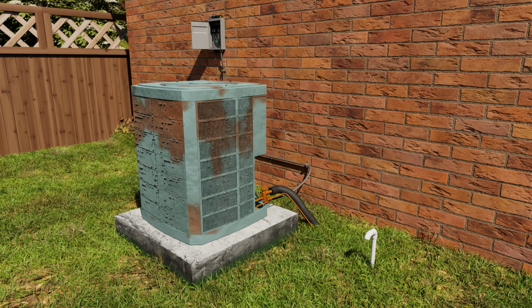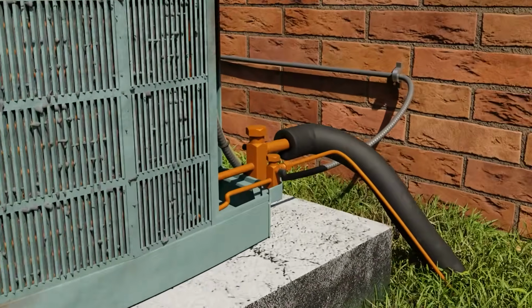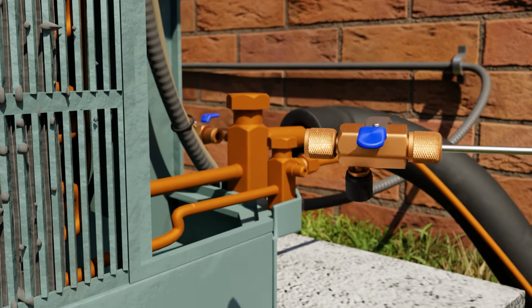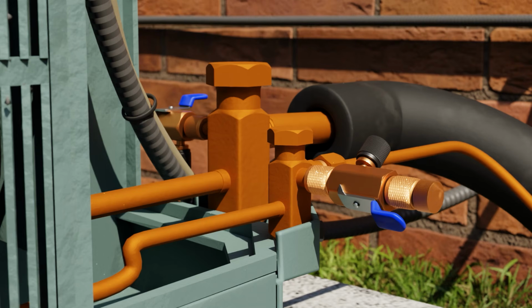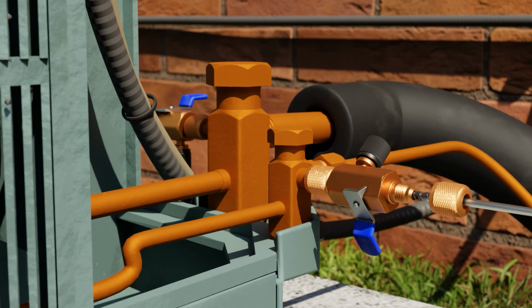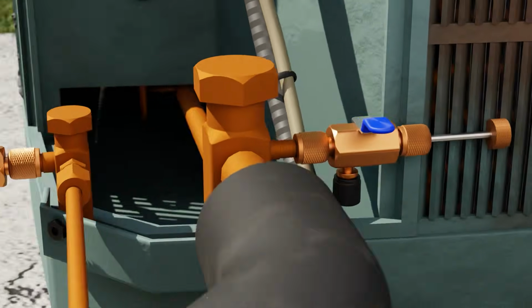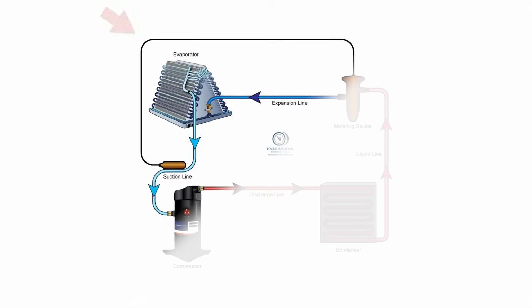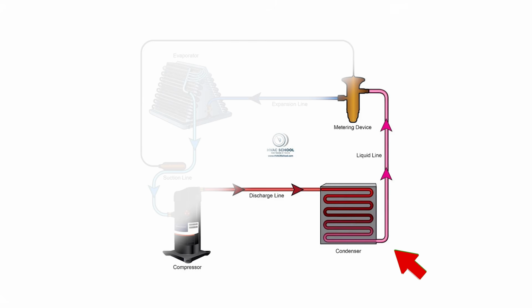Next, you're going to prepare the system for recovery. Here I'm showing the use of core remover tools to remove our cores. We remove cores to speed up the recovery so we don't have that restriction to refrigerant flow. You'd remove those Schrader cores from both service valves, the suction and the liquid. Suction being the low side and liquid being the high side.